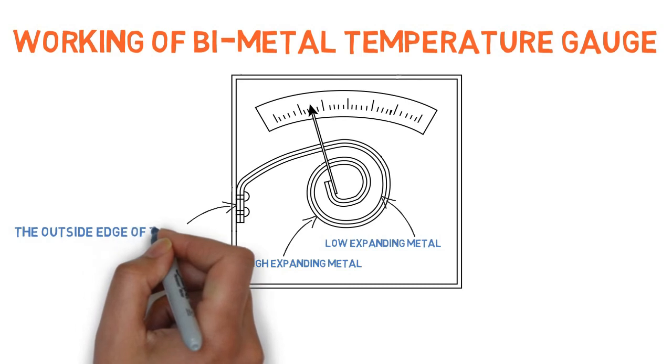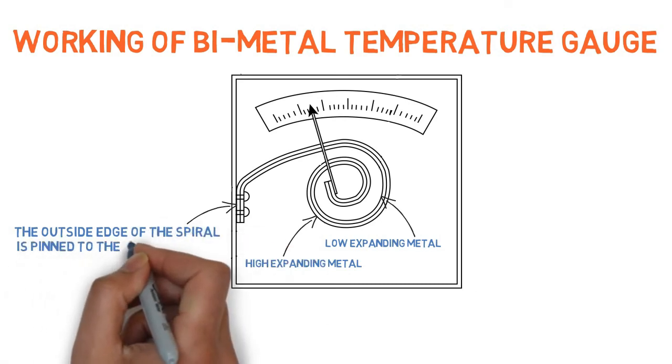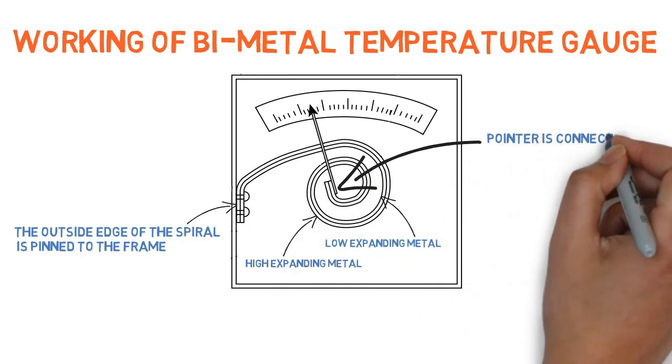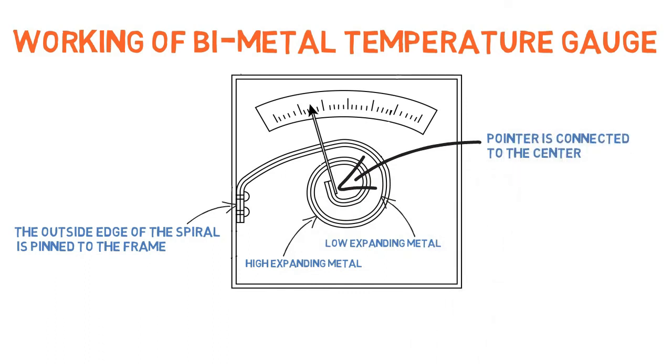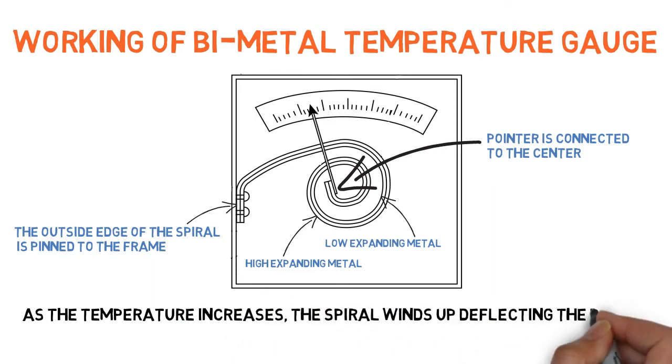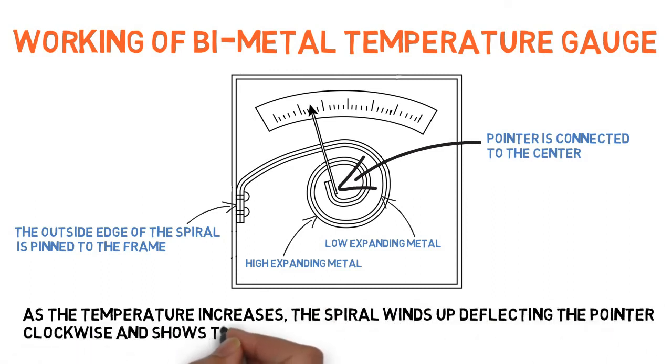The outside edge of the spiral is pinned to the frame. A pointer is connected to the center. As the temperature increases, the spiral winds up, deflecting the pointer clockwise and showing the temperature value.